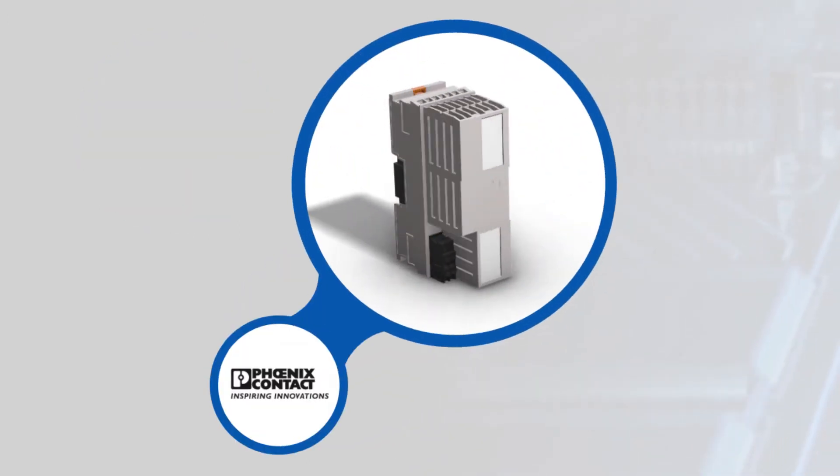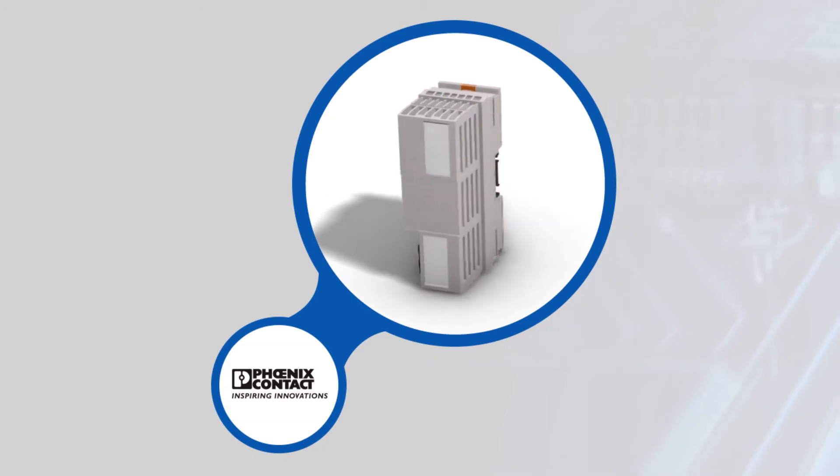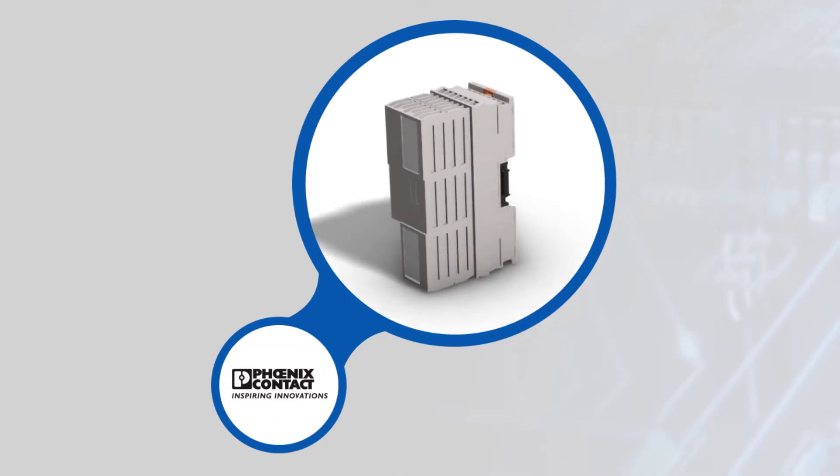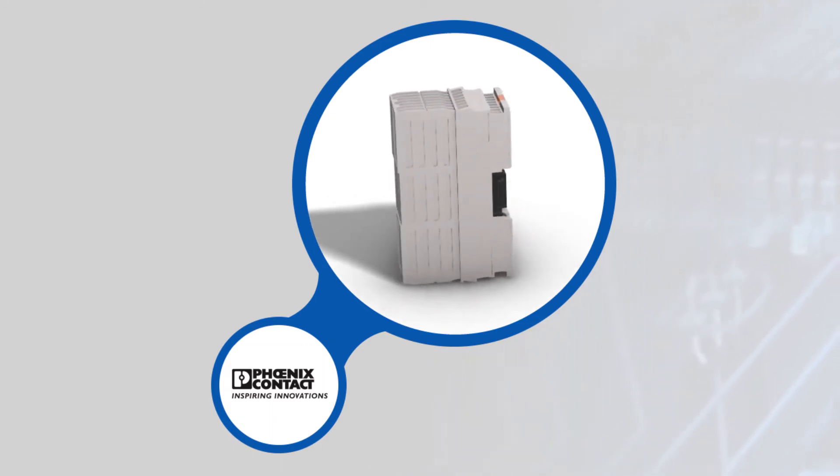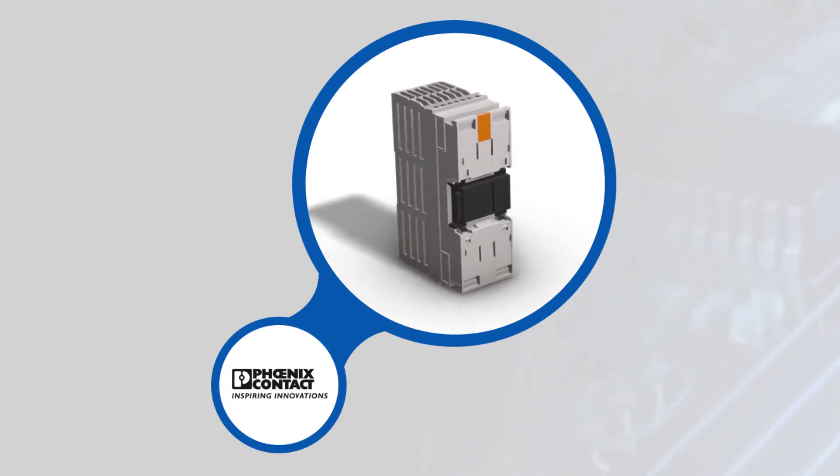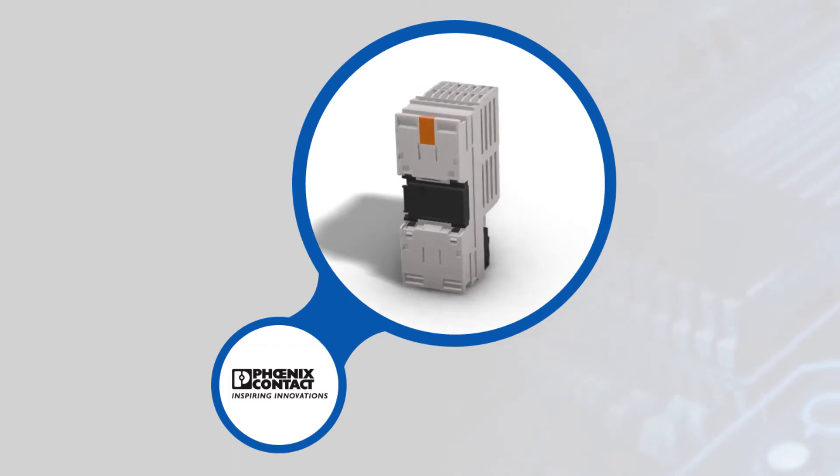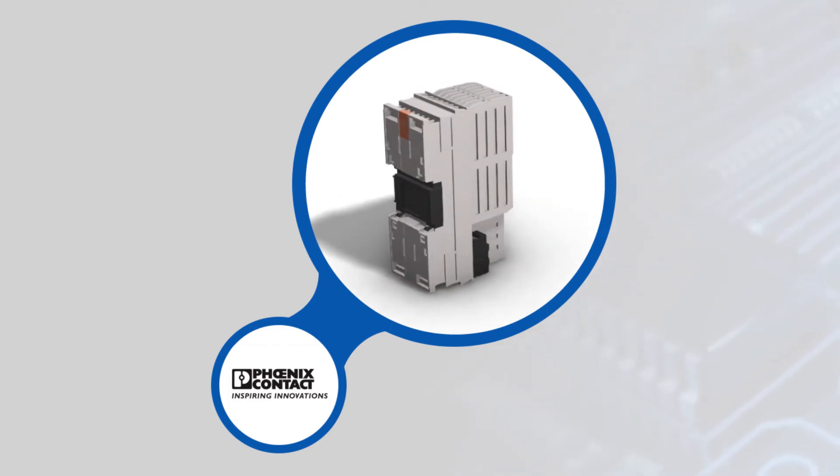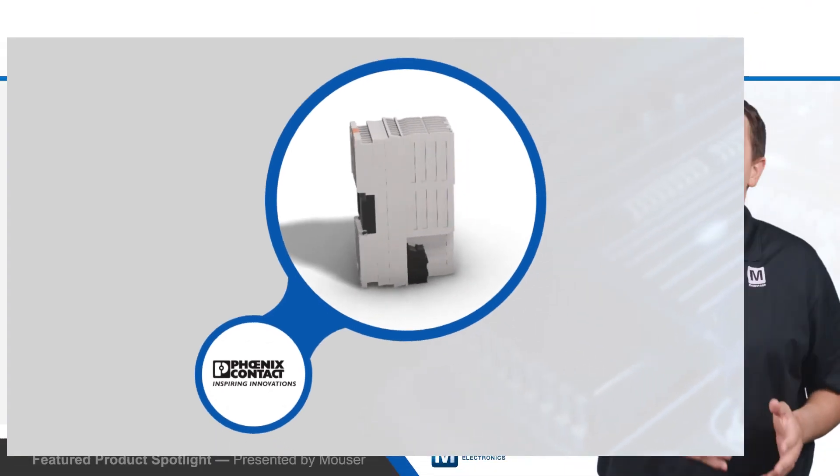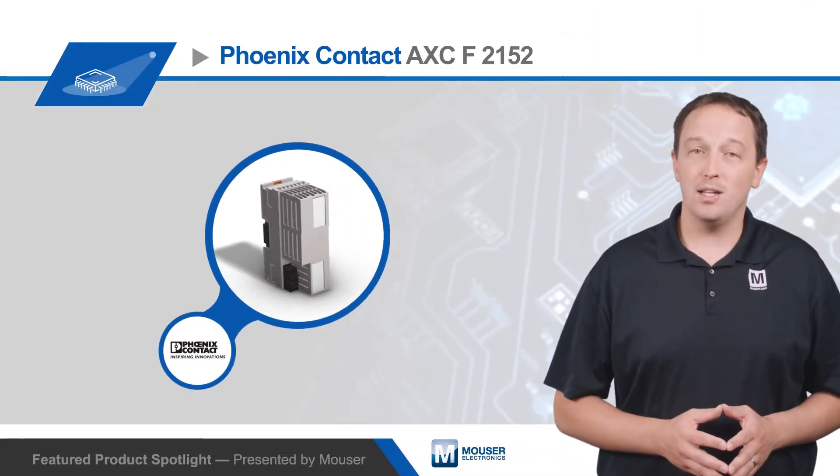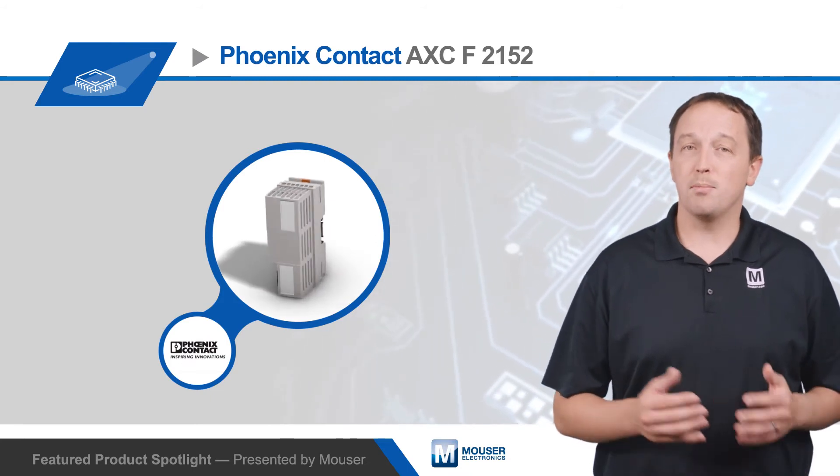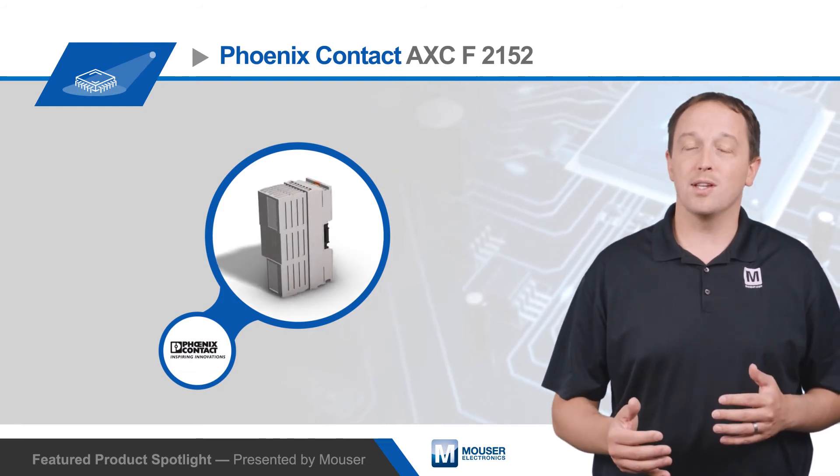The AXC F2152 controller has a hardened industrial-grade build for environmentally demanding applications, with the ability to withstand 30G shock, 5G vibration, 5% to 95% relative humidity, and temperatures from -25 to +60 degrees Celsius.